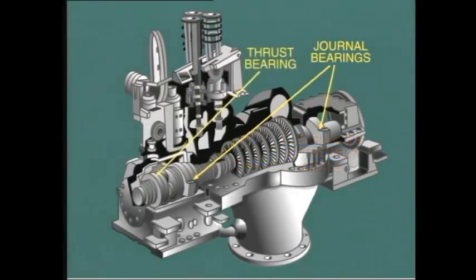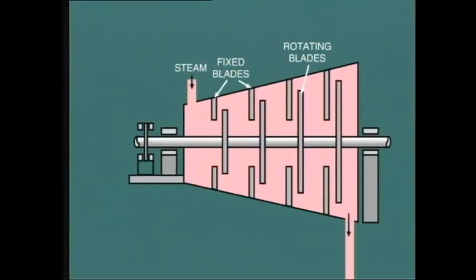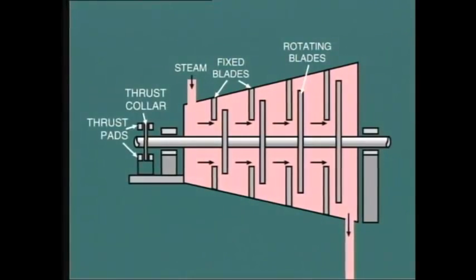A thrust bearing is located along with the journal bearing at the governor pedestal in order to locate the shaft and prevent movement in the axial direction. What do we mean by this? Well, in this single-cylinder arrangement, the flow of steam through the turbine tends to push the rotor towards the generator. If this thrust was not contained, the rotating blades could conceivably come into contact with the stationary blades of the next stage and cause quite a catastrophe. To prevent this occurrence, a fixed collar on the shaft is held in position by lubricated thrust pads.